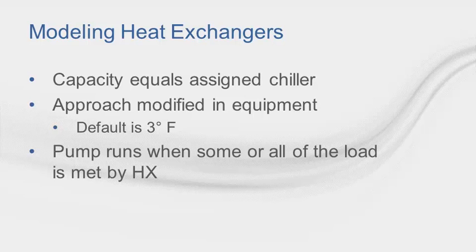A few important things to note about modeling heat exchangers in TRACE 700. TRACE assumes the capacity of the heat exchanger equals that of the chiller to which it is assigned. Heat exchanger approach is modified in the equipment library and then placed in the project via the chiller on which it was configured — the default is 3°F. The free cooling pump runs when some or all of the load is satisfied using free cooling.